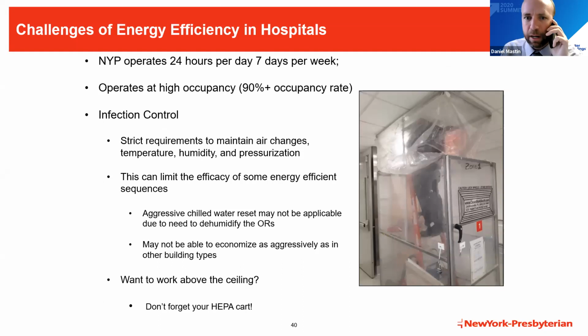Some of the challenges of energy efficiency in hospitals: completing projects. We're occupied 24 hours a day, 7 days a week, typically operating at 90% plus occupancy. Changing lights, for example, isn't as easy as it is in an office building. We can't just go in at 5 o'clock, change a bunch of fixtures, and then nobody's there. We have people there all the time, and we have infection control protocols we need to meet. In that picture, you can see one of our electricians working in a HEPA cart. Anytime we get up above the ceiling and pull a ceiling tile, we need one of those carts available. It's negatively pressurized and captures all the dust, preventing it from getting into patient spaces. A lot of the patients are immunocompromised, so this is a method of protecting them.